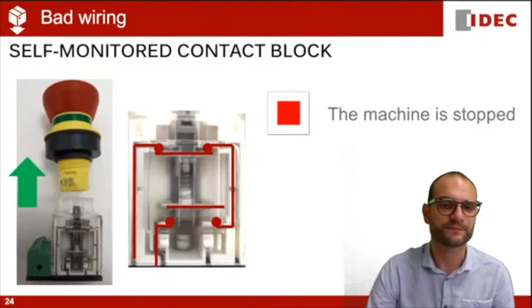The other solution is IDEC original safe break action. The spring is mounted the other way round compared to the regular e-stop. When properly installed and not actuated, the spring is compressed and the machine is running. If the button is pressed, the spring is released and opens the contact, stopping the machine in a safe state.